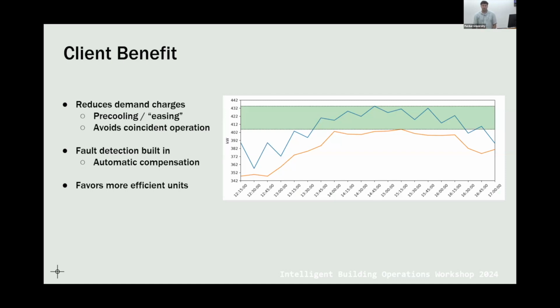There are two benefits, or two audiences which benefit from it. There's the client, which benefits from having reduced costs from their demand being reduced. In addition, when a unit is performing poorly, there's a built-in mechanism when you use model predictive control where a unit that is more effective at delivering the cooling load will compensate and will be prioritized in the algorithm and deliver cooling. So there are some built-in benefits to the client as far as comfort goes, not just demand.